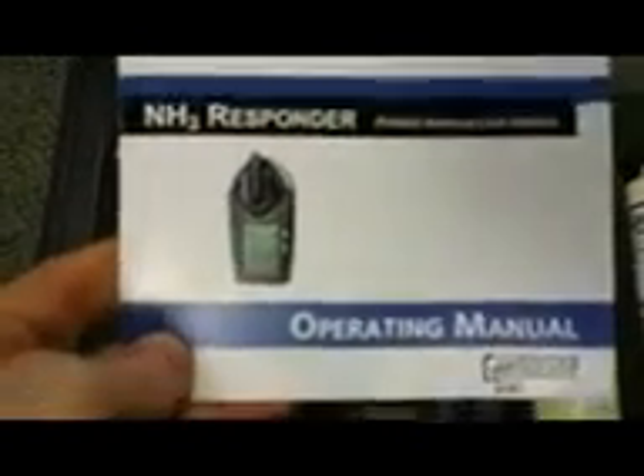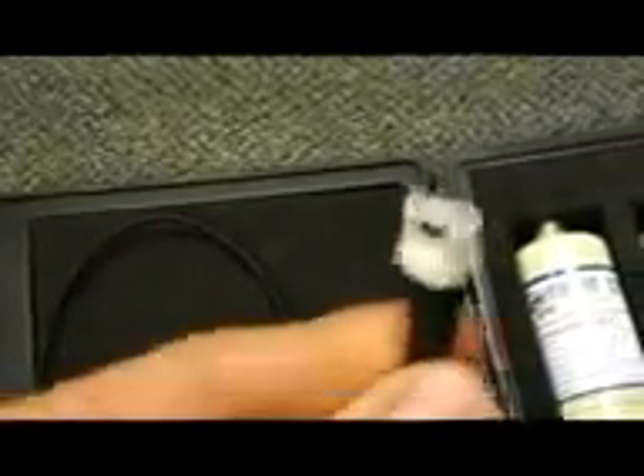We are going to cover how to calibrate your NH3 responder by Calibration Technologies. If you have not already located your book, NH3 Responder, get that out. You will need a book, a monitor, cord. This is called the demand flow regulator. It has an open and close valve at the top. You will also need, sometimes these things come assembled, sometimes they don't.